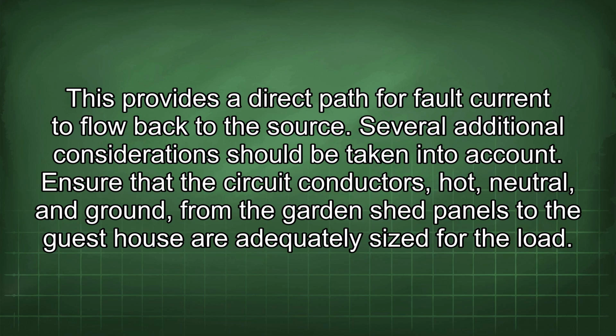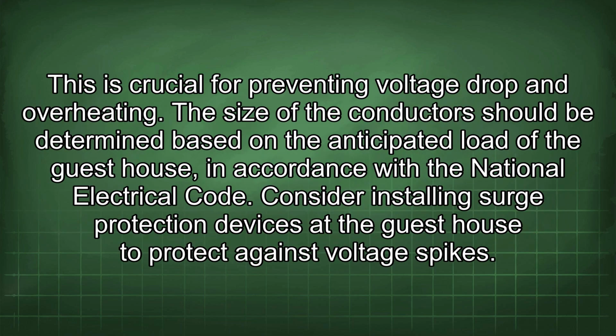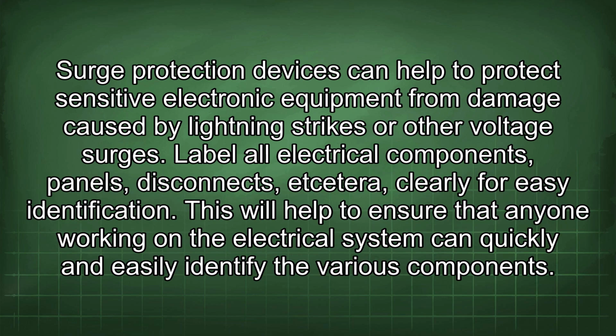Several additional considerations should be taken into account. Ensure that the circuit conductors, hot, neutral, and ground, from the garden shed panels to the guest house are adequately sized for the load. This is crucial for preventing voltage drop and overheating. The size of the conductors should be determined based on the anticipated load of the guest house, in accordance with the National Electrical Code. Consider installing surge protection devices at the guest house to protect against voltage spikes. Surge protection devices can help to protect sensitive electronic equipment from damage caused by lightning strikes or other voltage surges.